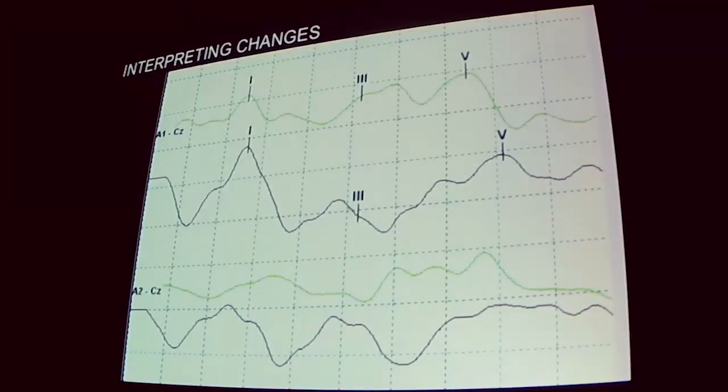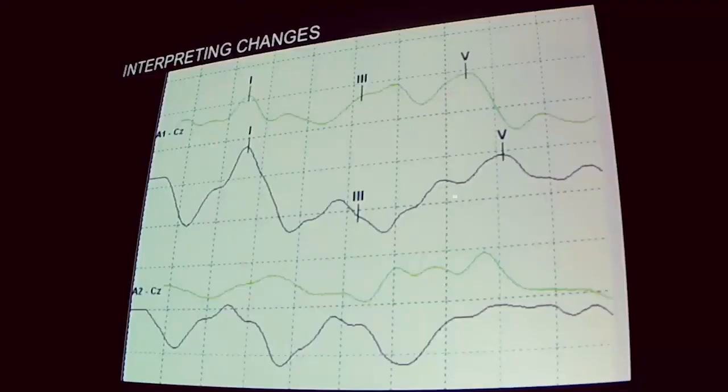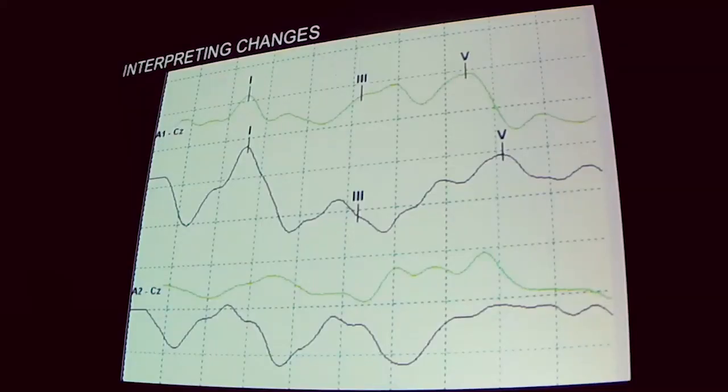So, as you can see here, shifts out. They took the retractor out. Again, you have to correlate it to a change. We knew they had the retractors in. Everything was fine. It was going perfectly. And then this wave 5 started to shift way out. And we said, hey, do you have your retractors in? Sometimes you can't see what they're doing. And they go, yeah. We tell them, and they took the retractors out, and everything came back to normal. So just be aware of that.